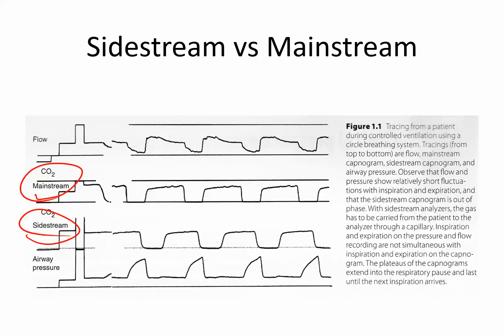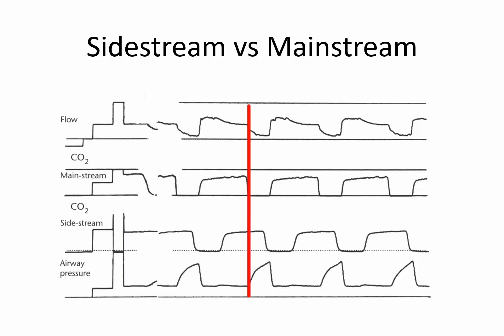This figure compares tracings from a mainstream and a sidestream capnometer, with the bottom trace showing airway pressure. When inspiration starts — indicated by rising airway pressure — the mainstream capnometer gives an immediate loss of CO2, which makes sense because the gas flowing past it should be devoid of CO2. There is a time lag, however, with the sidestream capnometer. You know this because when you've struggled to intubate a patient and are unsure if the tube is in the trachea or esophagus, it can feel like it takes forever for the CO2 waveform to appear.